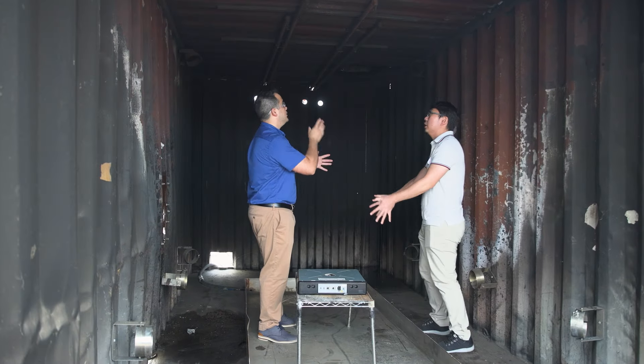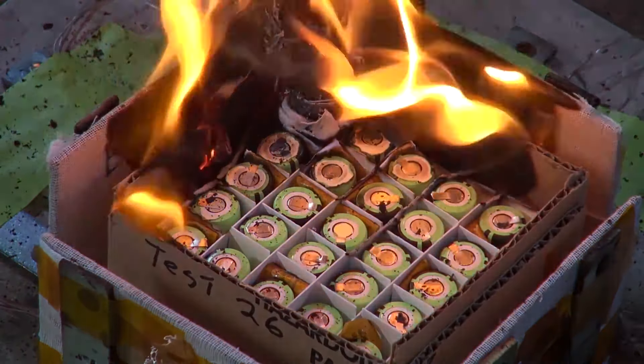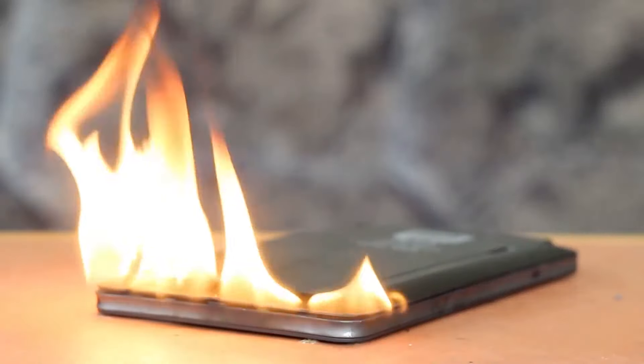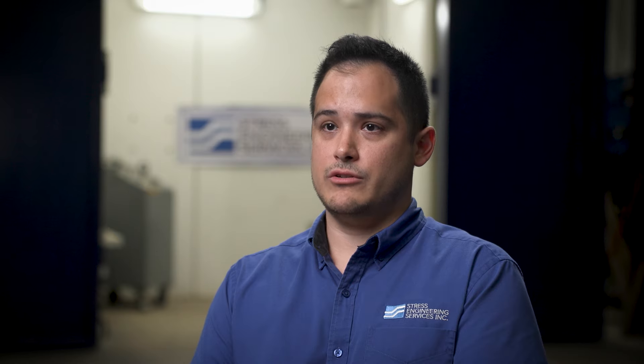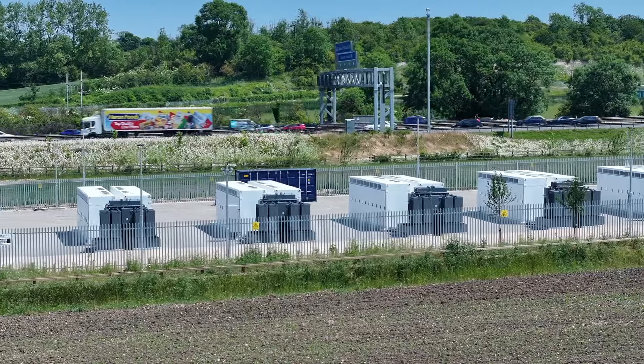And finally, to look at fire suppression with respect to this particular battery chemistry. Thermal runaway can propagate from a single cell through an entire pack, resulting in a lot of energy release. All of the chemical energy that is in the cell can be released in the form of heat, and the gases that are generated are flammable and combustible. That can result in rupture, fire, or explosion of an enclosure, presenting a lot of hazards to both people and infrastructure.